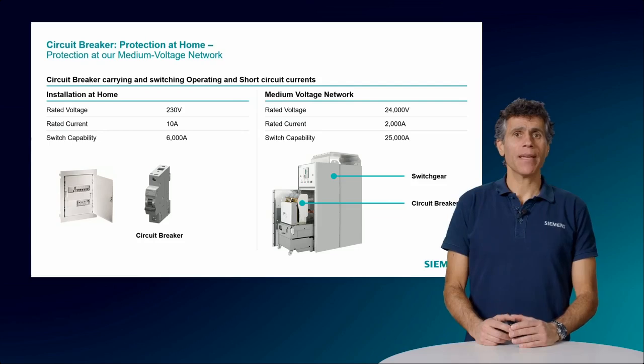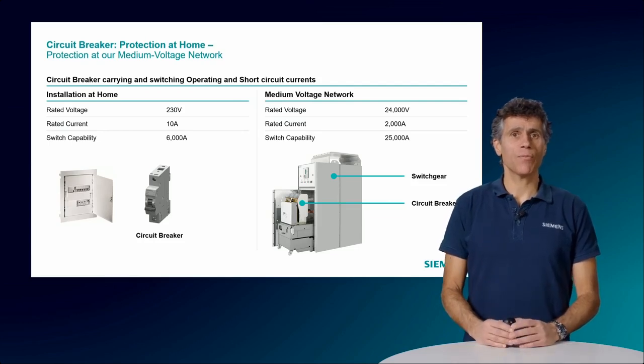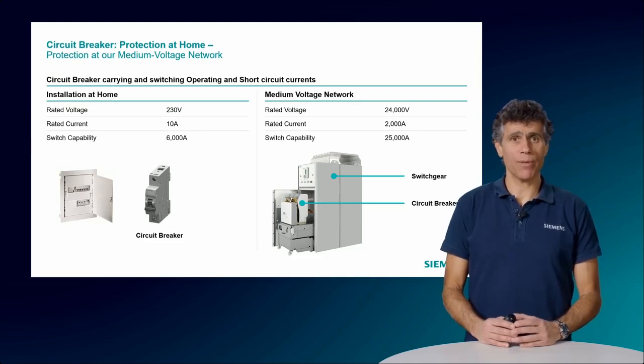We begin by comparing the specifications of a circuit breaker at home versus those in medium voltage networks. At home, a typical setup might include a circuit breaker with a rated voltage of 230 volts and a rated current of 10 amps, possessing a switch capability of 6000 amps.